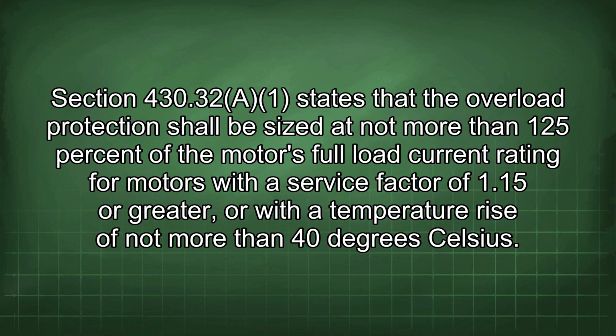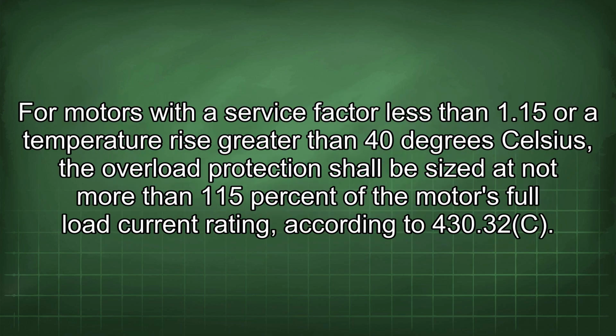Section 430.32(A) states that the overload protection shall be sized at not more than 125% of the motor's full load current rating for motors with a service factor of 1.15 or greater, or with a temperature rise of not more than 40 degrees Celsius. For motors with a service factor less than 1.15 or a temperature rise greater than 40 degrees Celsius, the overload protection shall be sized at not more than 115% of the motor's full load current rating, according to 430.32(C).